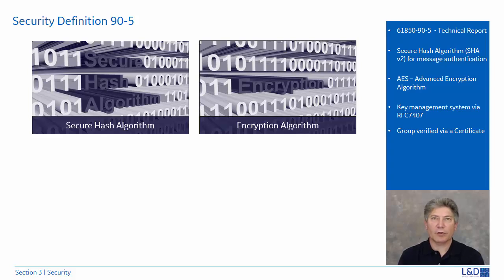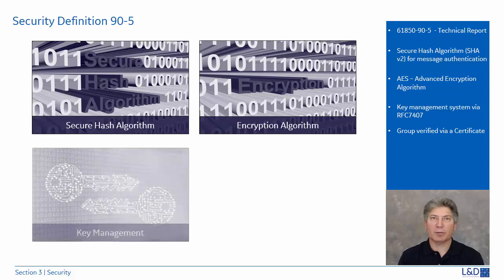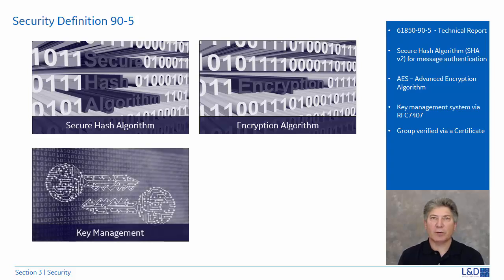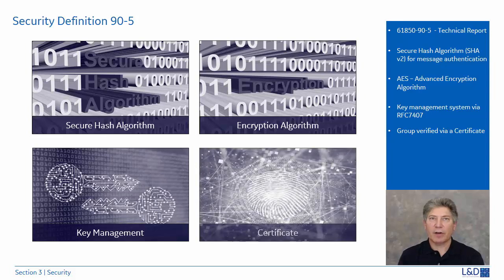The technical report also defines a key management system. Using RFC 6407, the Group Domain of Interpretation, the system manages the keys to all members in the group — meaning the publishers and subscribers. This key is also incorporated when generating hash and encryption algorithms. It also defines that the group members are issued a certificate once they have been verified for authorization and authenticated as valid members in the group.